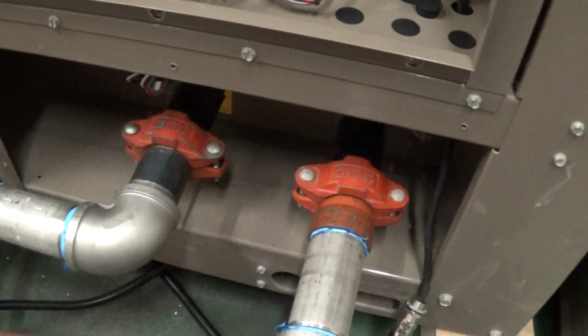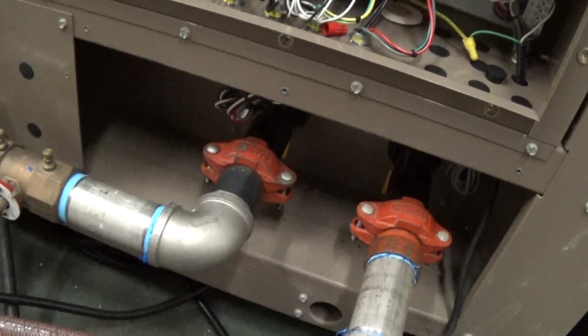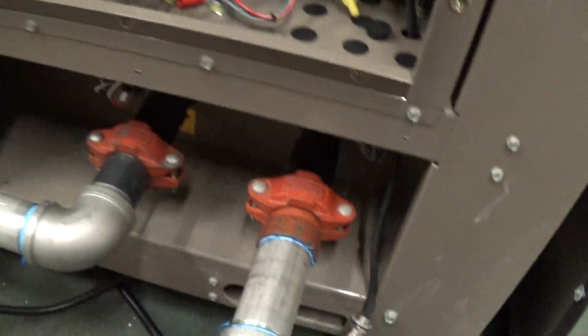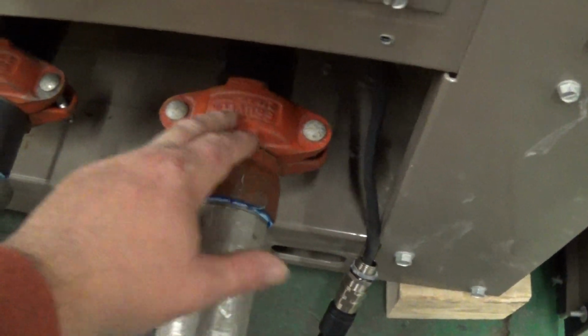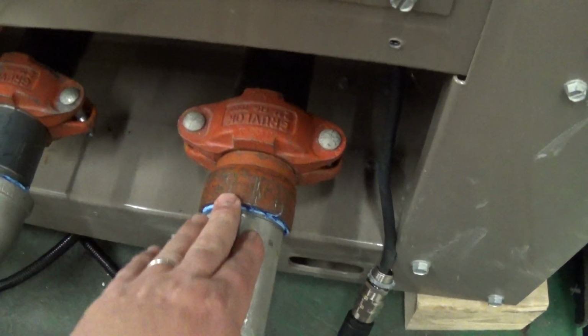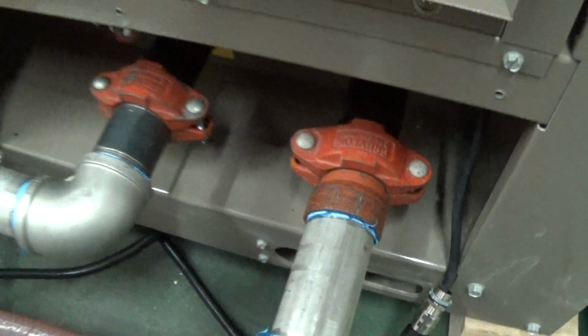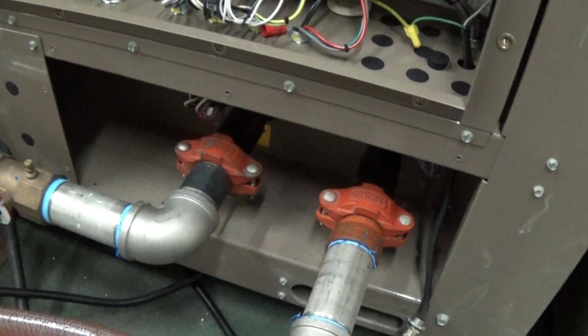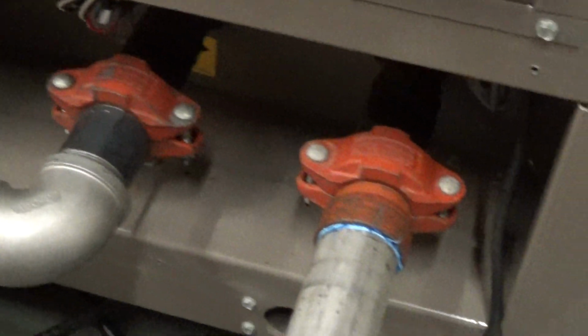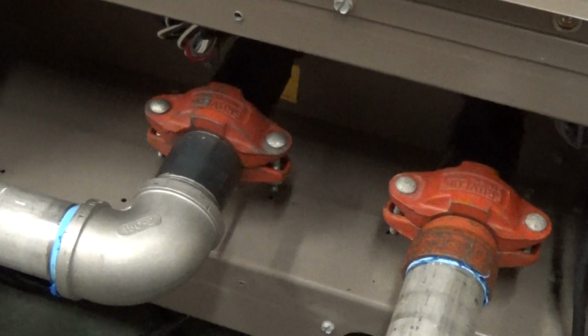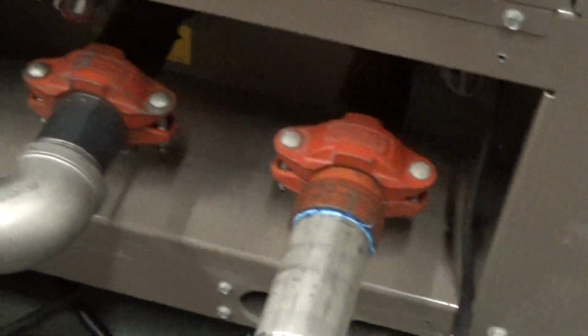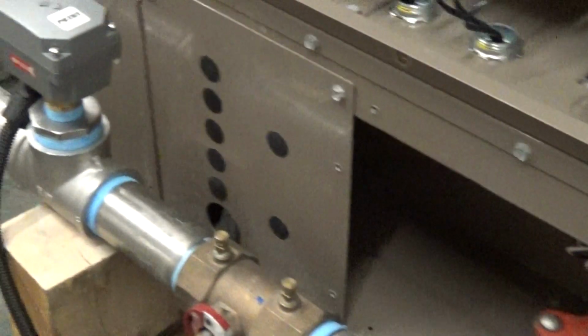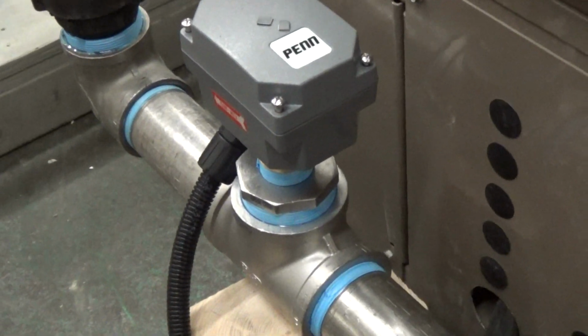This unit comes with 2-inch connections, grooved connections. So you use these Victaulic type clamps here to transition from the 2-inch grooved connection over to NPT if that's what you truly want to do. We can help you source those fittings if you need them. The chiller comes with a flow switch, so that'll come loose in the box.